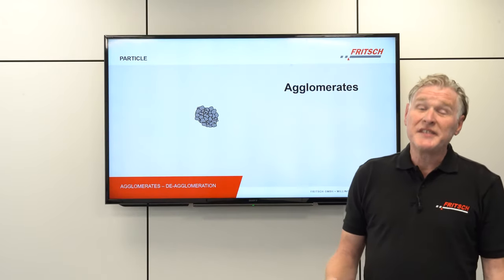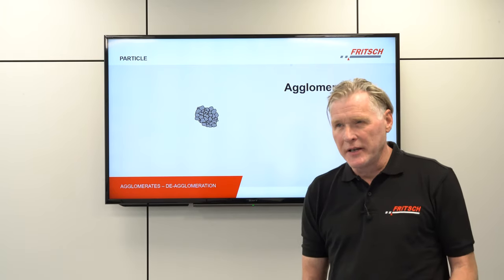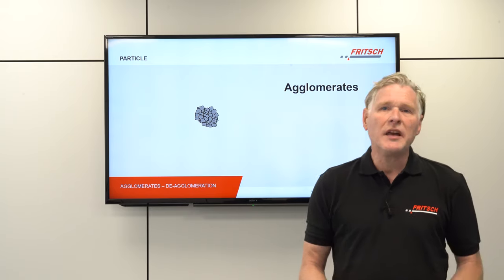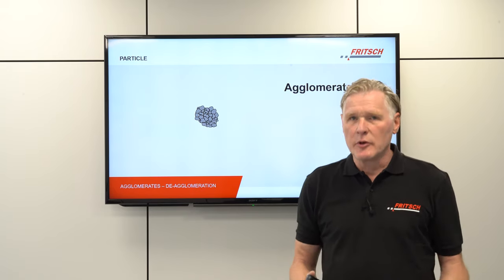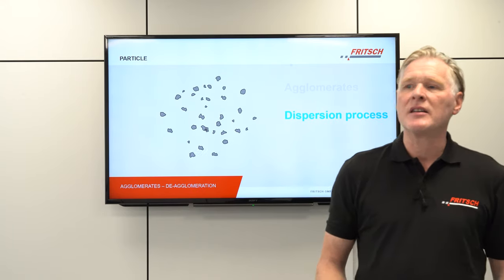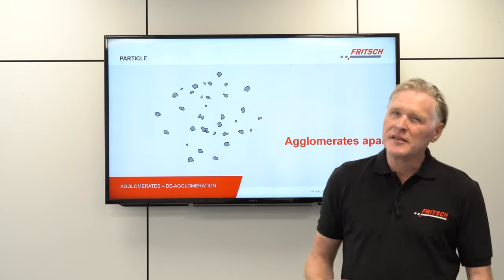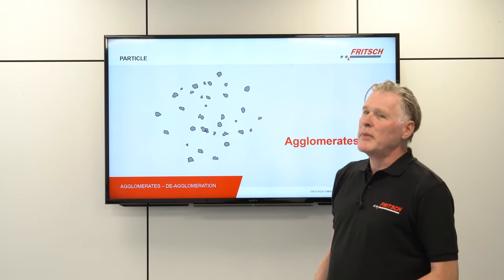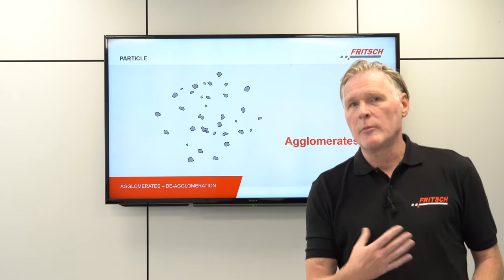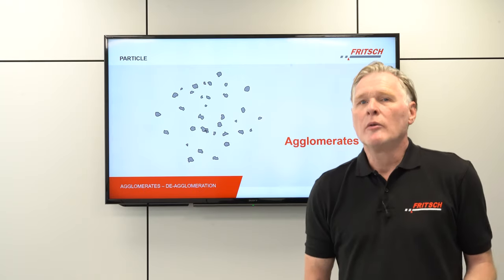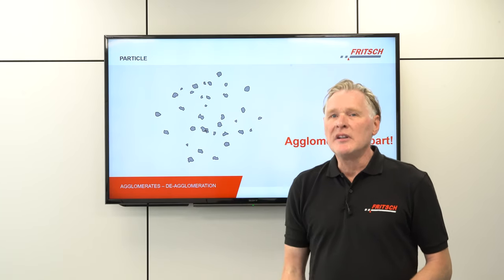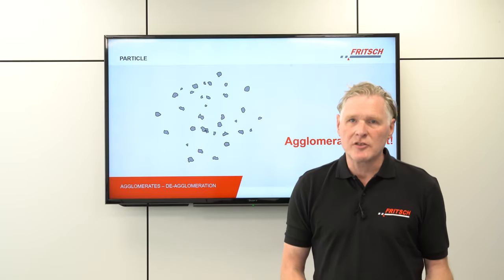In most cases particles will form agglomerates — particles stick together. In most cases you will not be interested in the size of your agglomerates but want to know the size of the separated particles, which means you need to take those agglomerates apart — what we call a dispersion process. It may happen that you cannot take the agglomerate completely apart; some fraction may remain. This is one of the main challenges for the user: to de-agglomerate and disperse the sample material in your instrument or during preparation.